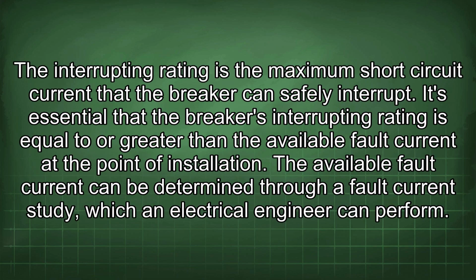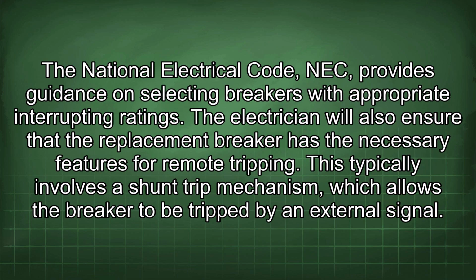The interrupting rating is the maximum short circuit current that the breaker can safely interrupt. It's essential that the breaker's interrupting rating is equal to or greater than the available fault current at the point of installation. The available fault current can be determined through a fault current study, which an electrical engineer can perform. The National Electrical Code, NEC, provides guidance on selecting breakers with appropriate interrupting ratings.